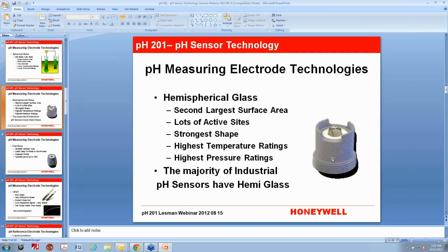And that is going to be your strongest angle. So if you have a really high temperature, or if you bump it, it's going to be less likely to break along that weld line. It has the highest temperature and highest pressure ratings for a glass measuring electrode. Most of the pH sensors that I see out in the processes are hemispherical style, and that's probably because it is the most robust. It's not always the right one for your process. This all depends on your process conditions and your application, etc. But this is, I would say, the most robust of the glass measuring electrodes.